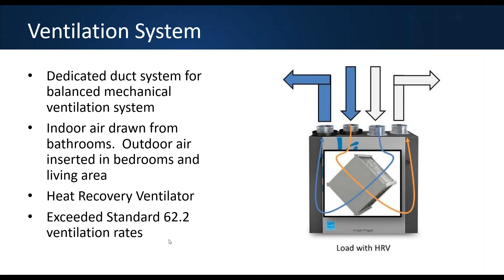Our ventilation rates in that first year exceeded 62.2 standards, because this fan had discrete settings — 1, 2, 3. Setting 2 didn't meet 62.2, setting 3 exceeded it, so there wasn't a perfect match. We ended up bringing in more ventilation air than needed by 62.2, but didn't want to go below it.